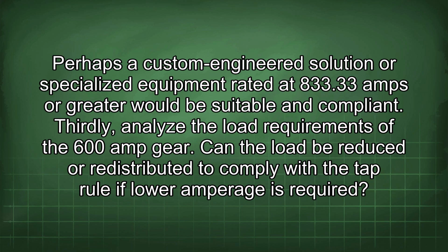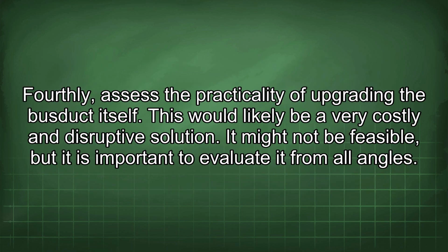Thirdly, analyze the load requirements of the 600 amp gear. Can the load be reduced or redistributed to comply with the tap rule if low amperage is required? Fourthly, assess the practicality of upgrading the busduct itself. This would likely be a very costly and disruptive solution. It might not be feasible, but it is important to evaluate it from all angles.